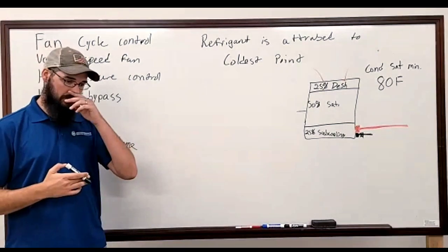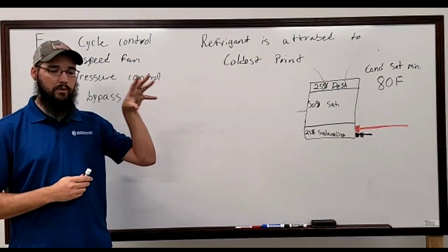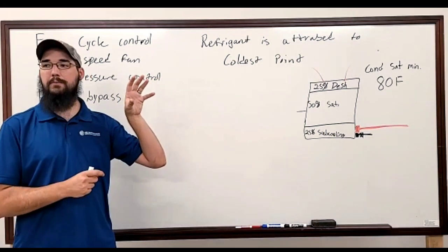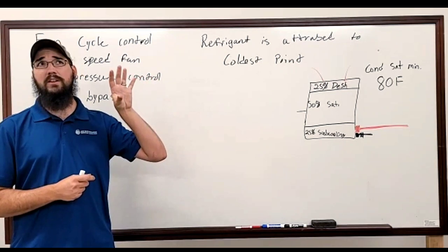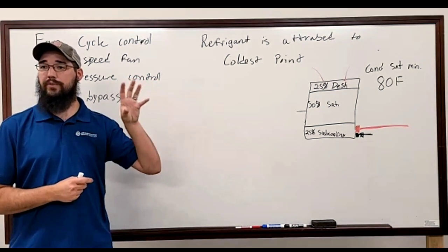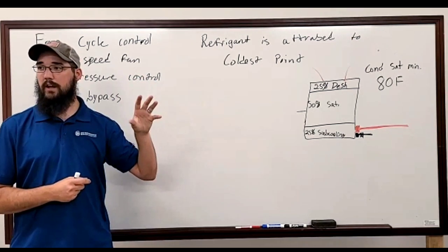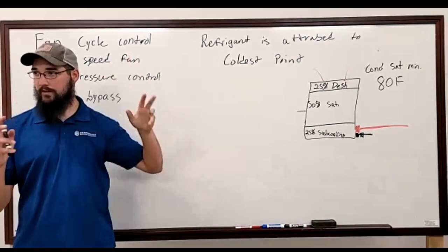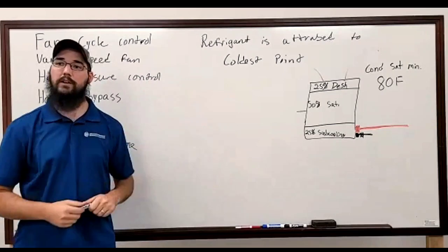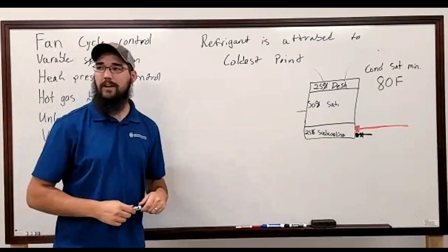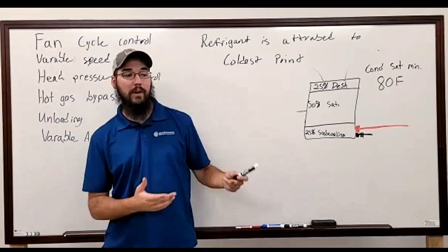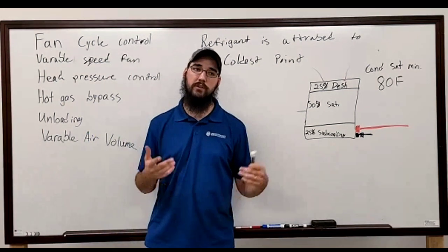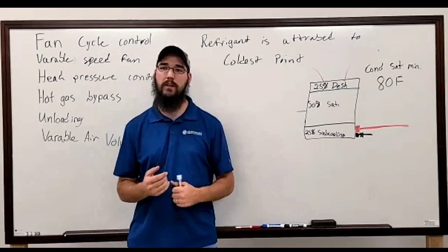Trane has actually produced motors where they have a fan motor controller installed in the outdoor unit, and it will monitor head pressure, and I think it does it through resistance. It will control fan speed based off of resistance, kind of like a regular motor speed controller we would install on a VAV or a fan power box. Same concept, just 10 times the price because it's got a Trane motor on it. But anyway, those are probably the two most common versions we see on regular duty, light duty type equipment.